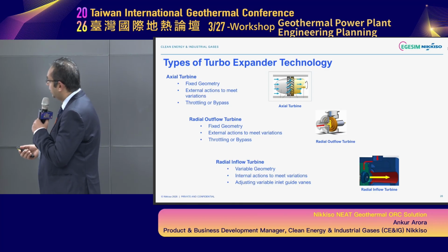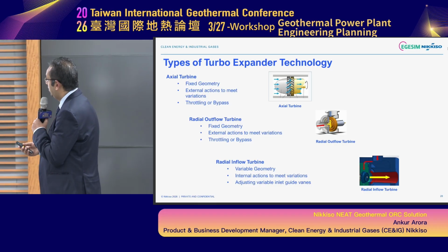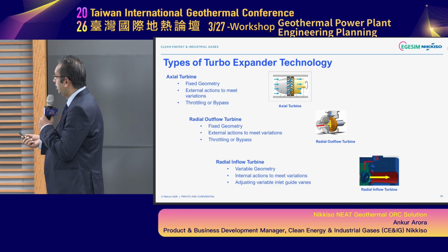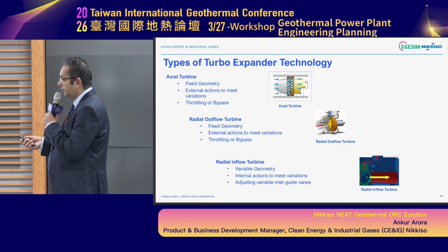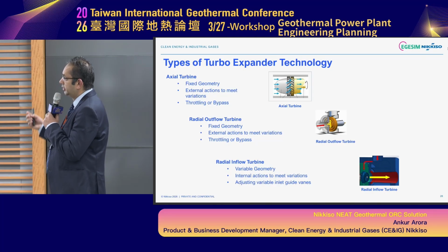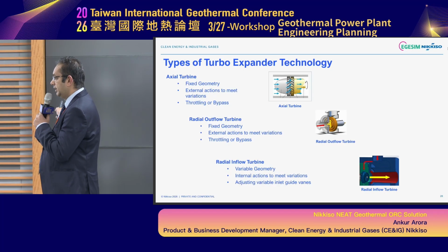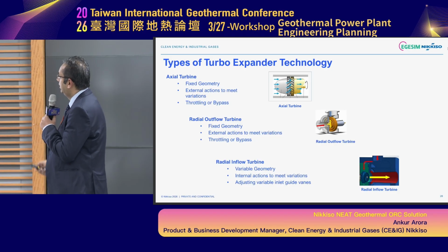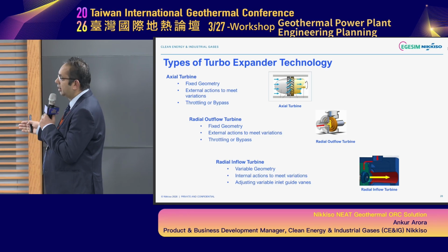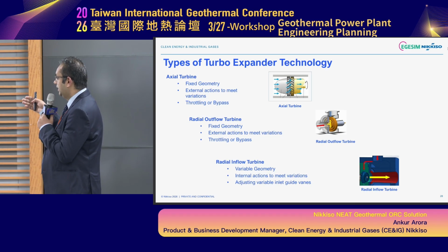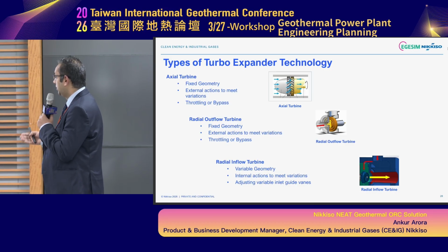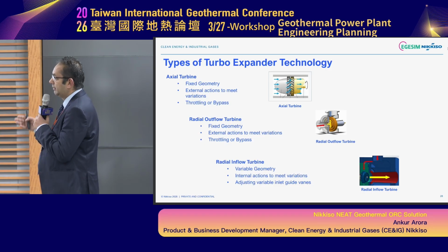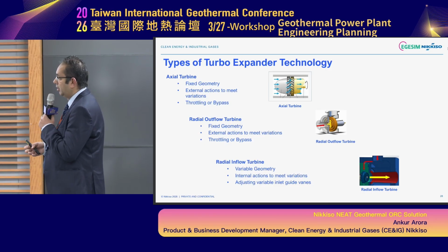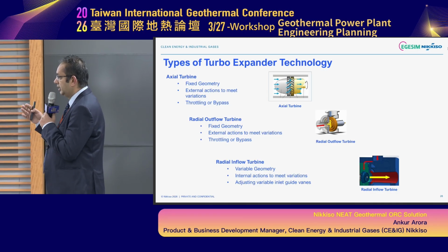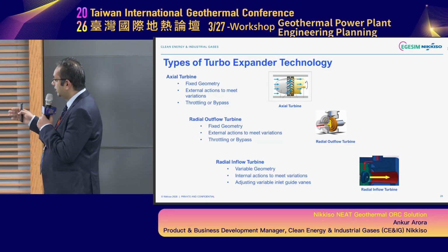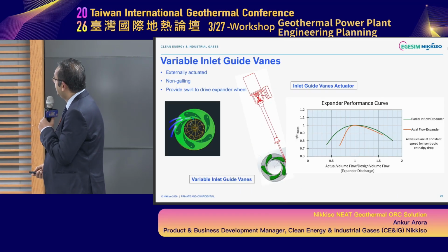There are three different types of turbo expander technology: axial turbine, which is quite widely used in geothermal; radial outflow; and radial inflow. Within Nikkiso, we use radial inflow turbines — the flow enters at 90 degrees and we pass axial flow out from there. This also caters to our hydrocarbon needs; we manage a lot of hydrocarbon applications much better with the radial inflow turbine. If there are any variations in pressure or temperature of the reservoir, or changes in minimum/maximum design criteria, it's far easier to handle in radial inflow than in an axial flow unit.